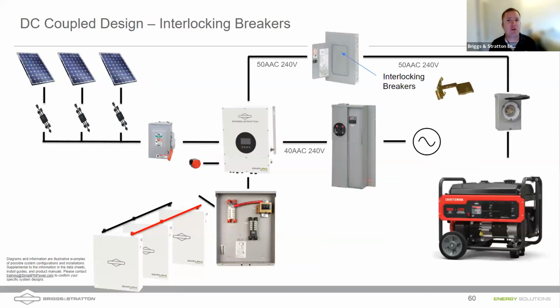This is what it might look like for a portable generator. We still have our AP Smart devices with our solar panels on the left, feeding DC into our inverter there. We have some batteries on the bottom, grid, non-backed up loads. But in this example, we're going to take a portable generator and put some interlocking breakers in the critical load sub panel, which is near the top. If the batteries are starting to go low and there's no solar to recharge the batteries, what we can do is start up the portable, flip the interlocking breakers, and allow the generator to then power the loads.